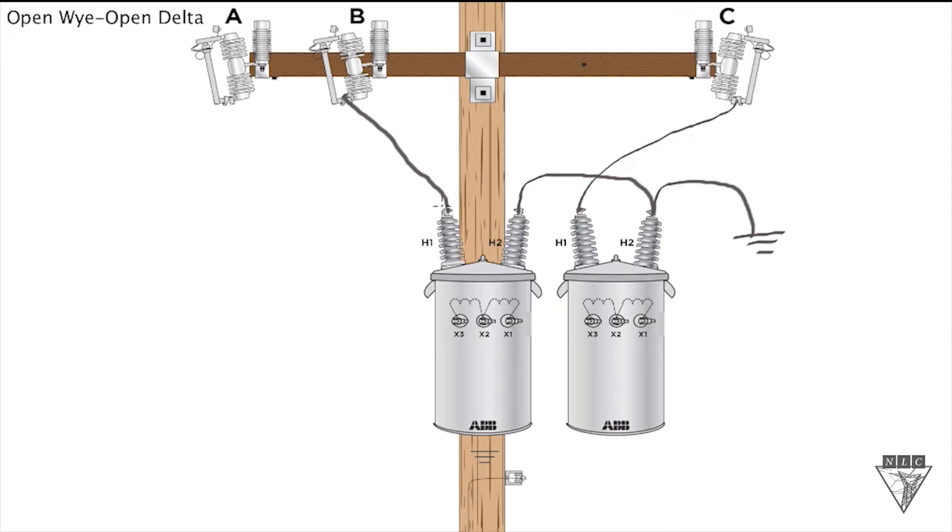You could just as easily go to A phase instead of B phase here. It doesn't matter, just depends on what they're looking for. So this is the primary Y connection. Your H2 bushings are tied together and then tied to ground, and then you utilize just two of the phases. We use C phase and B phase. That's our primary connection.